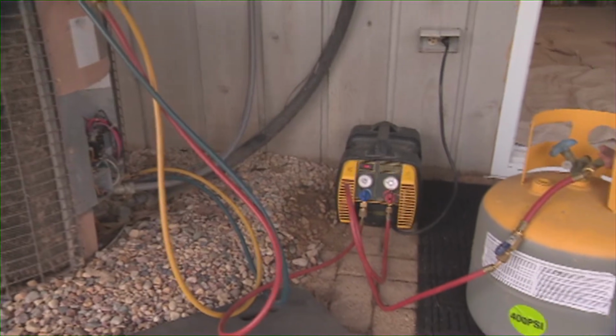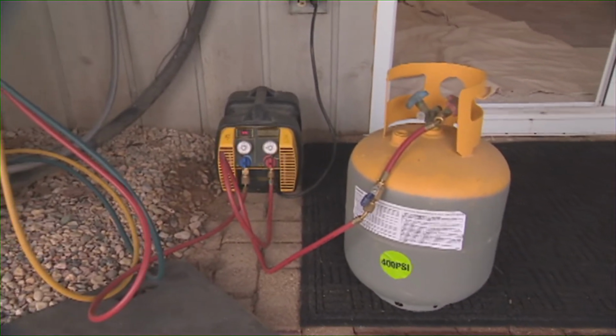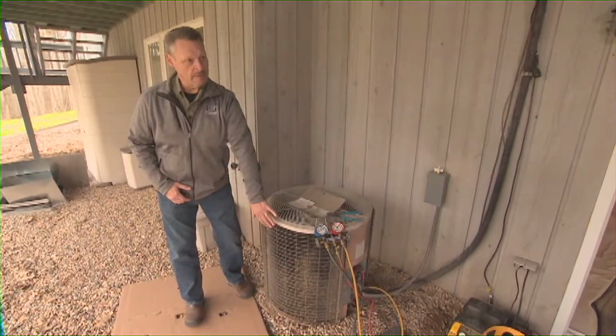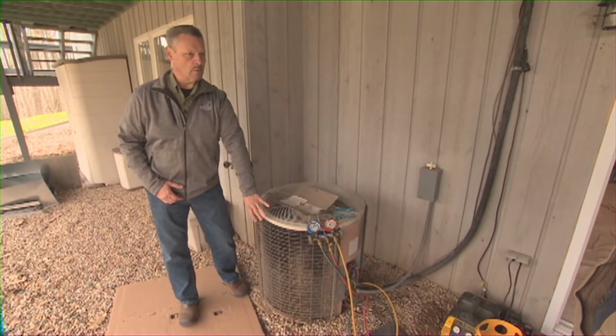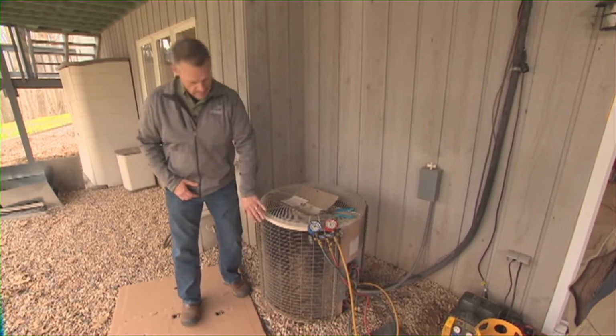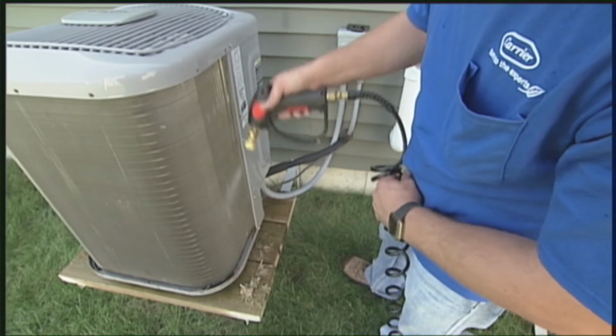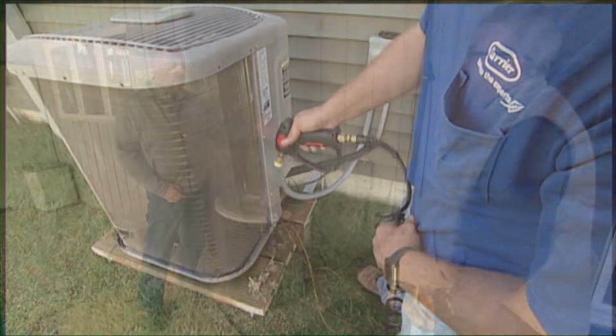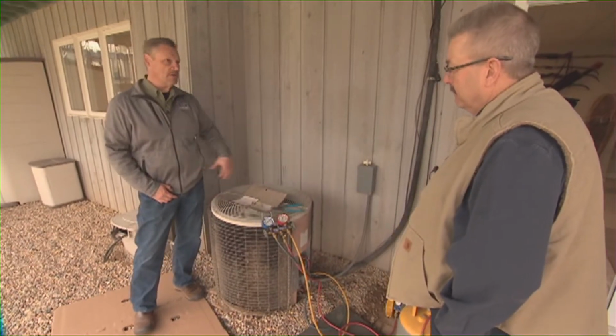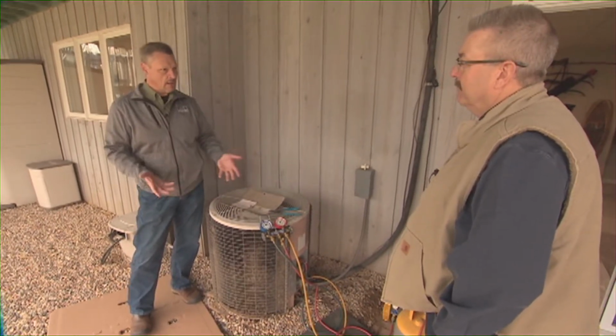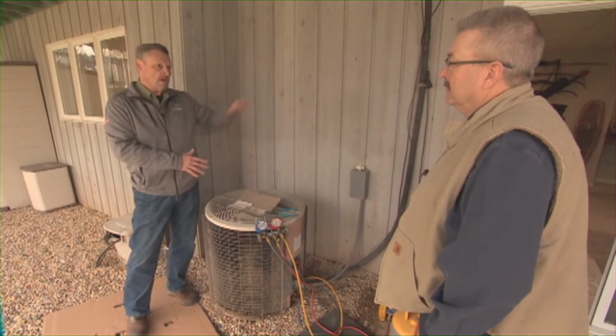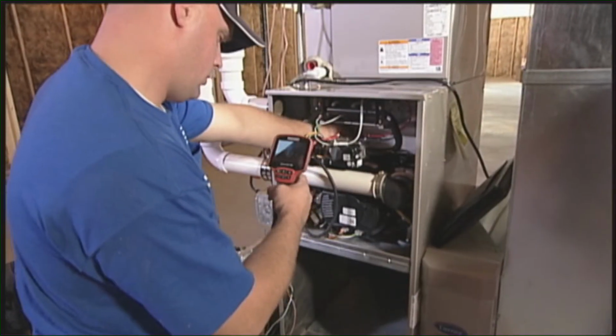This unit has also seen a lot of use and lack of maintenance, which was noted when we met with the homeowners. The amount of dust, dirt, and debris here, keeping that clean is part of proper maintenance, and you don't want to use a pressure washer for that. You want to use a regular spray hose, or set up preventative maintenance with your heating contractor. That will keep this in good operating condition and keep the efficiency of it and the furnace up to a higher level for the life of the equipment.